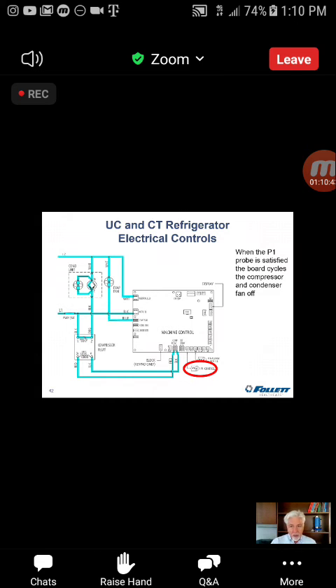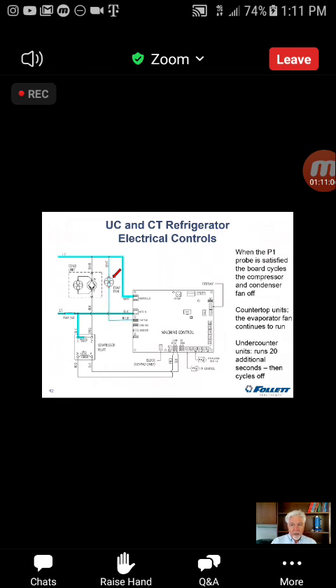So when we've pulled down the temperature that is detected by the P1 probe, all that happens is the control board shuts off the power going to the coil of the relay, and then of course the contacts open and the relay drops out. Now at that point, on countertop units, that evaporator fan continues to run. But on the undercounter, remember that setting I was mentioning, the fan delay, it's going to run for an additional 20 seconds and then it will cycle off.